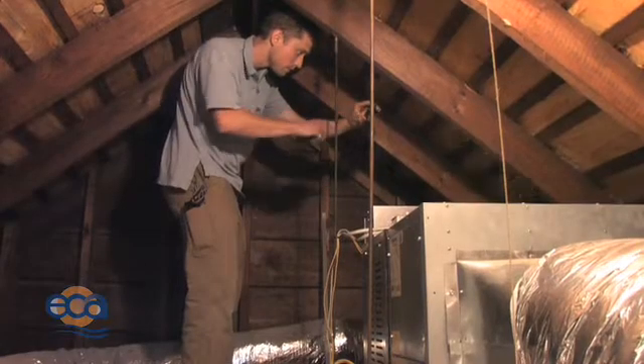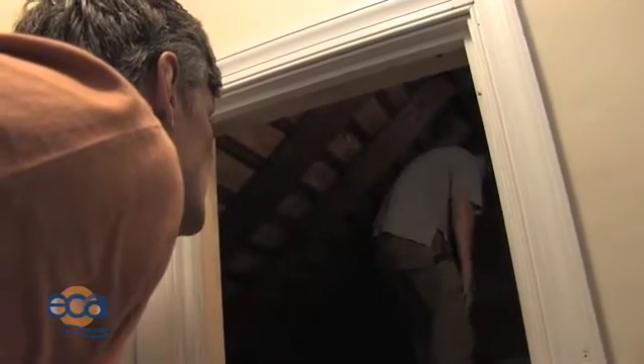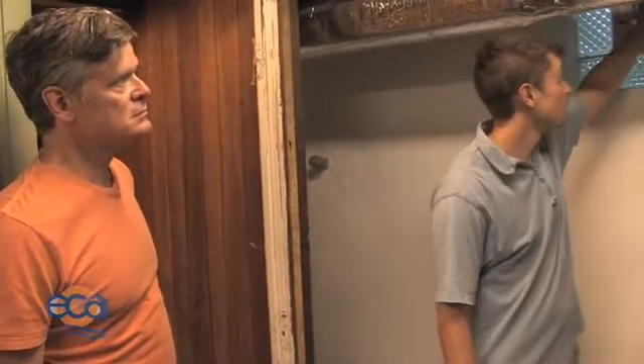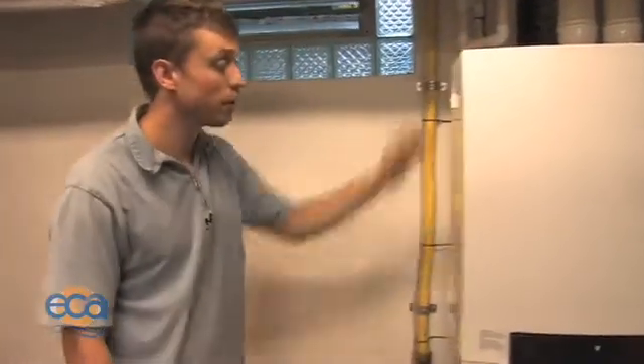Here's a secondary attic space and you have what looks like an air handling unit in here. There's plenty of ductwork winding around and then some fiberglass batt underneath. I had some questions about solutions that would help keep the heat from penetrating the roof and getting into this space and essentially heating the living space. The best solution might be to just foam the roof, foam the side walls, and just sort of bring this area into the conditioned space. This is a sealed combustion system — a very efficient system. This is not what we typically see in Philadelphia.